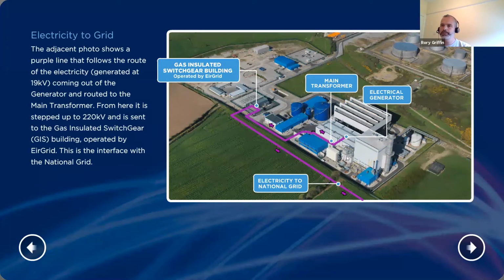On the electrical side, our generator is located here in the turbine hall. The terminals of the machine are at 19 kV, so the 19 kV bus ducts come out here to the side of the building. They come down here to the step-up transformer, where they're stepped up to 220 kV. Then there's a 220 kV cable coming around the site here to the GIS building. So this is our electrical connection to the grid.